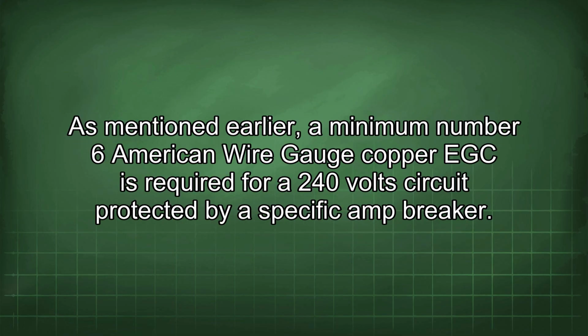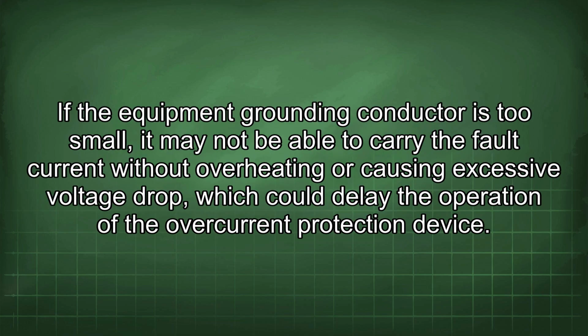As mentioned earlier, a minimum number 6 American wire gauge copper EGC is required for a 240 volt circuit protected by a specific amp breaker. If the equipment grounding conductor is too small, it may not be able to carry the fault current without overheating or causing excessive voltage drop, which could delay the operation of the overcurrent protection device.